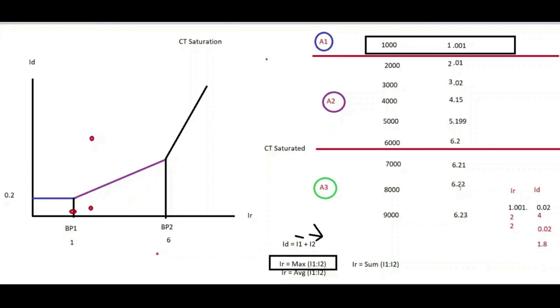What is your restraint current? One side 8, one side is 6.22. So your maximum current is 8 amps. 8. So plot 8, 1.8. So this point is going to be 8, 1.8. So somewhere here it will still be below the curve. So you are able to understand this 8 is more than your saturation point. And when we move towards the saturation region, we have created more area for restraining from tripping. This is called as the CT saturation algorithm. This is widely used in all the type of relays, in all the type of protections which involves unit protection. Even non-unit, it is applicable.